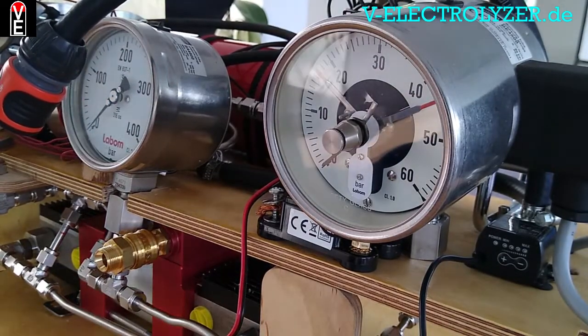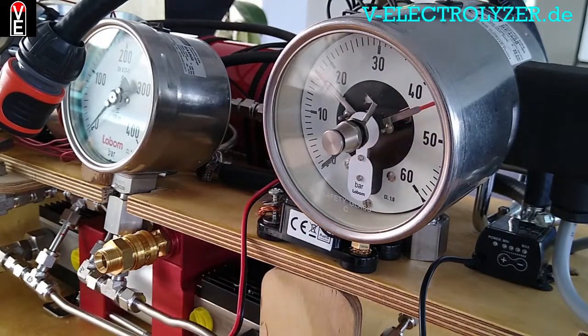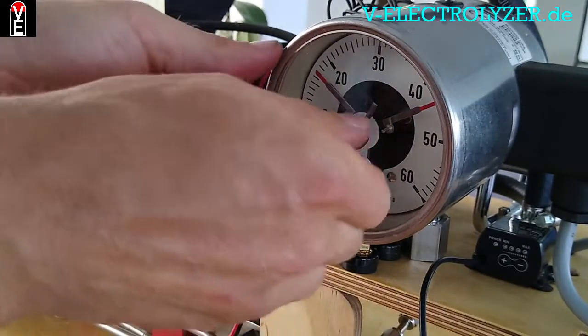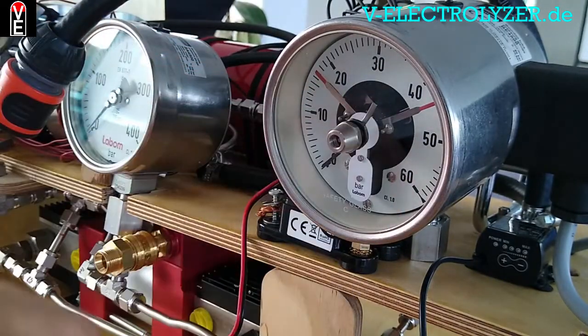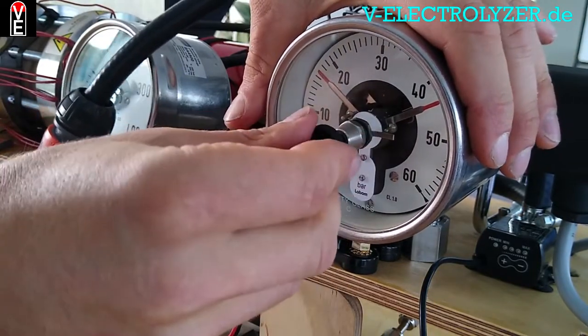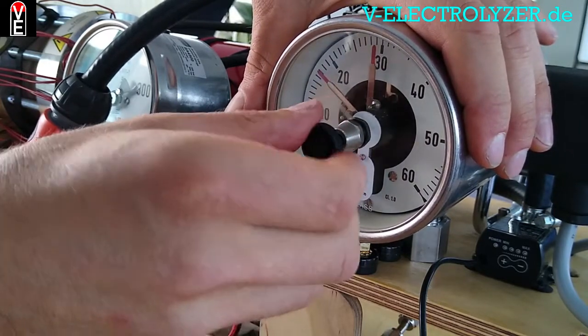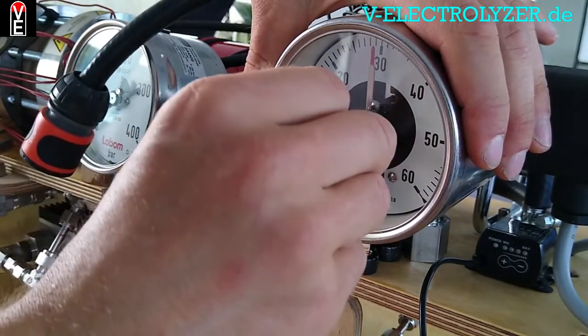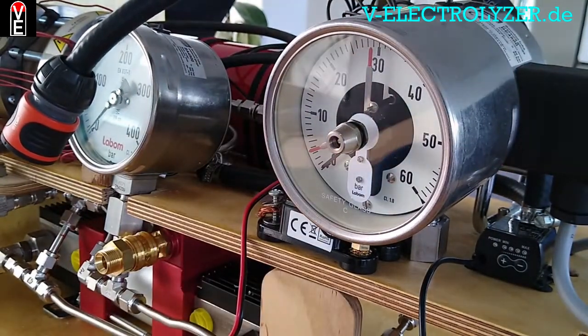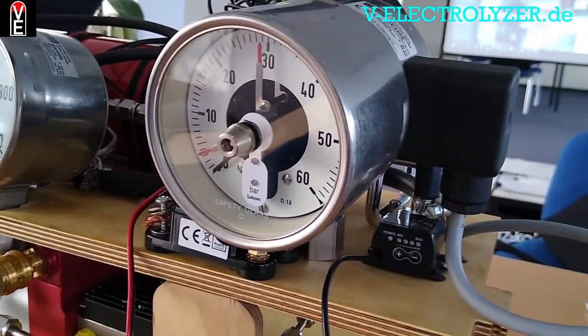The first step is to start compression at 30 bars. I will show you. This comes with a little key. You unscrew this cover — this dust cover — and you set it up: 1 to 30 bars to start, and you want to stop the compression cycle at, let's say, 40 bars. This electrical cable will go to a relay.